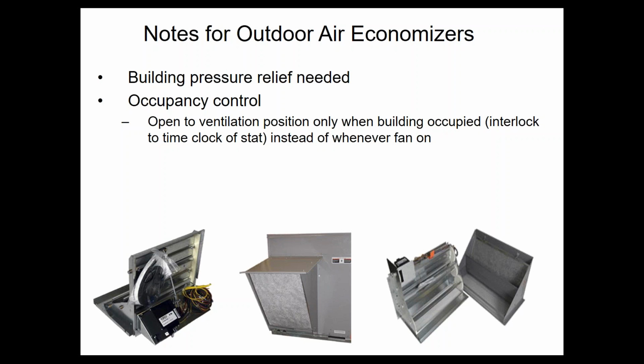When that happens, every time the fan goes on a packaged rooftop unit, the damper goes open to ventilation position, even if the reason the fan is going on is because you have a heating or cooling call for setback in the middle of the night. So every rooftop you probably ever designed, installed, or serviced is opening up its ventilation damper in the middle of the night when there's no people there for no reason whatsoever. The energy code no longer allows you to do that.